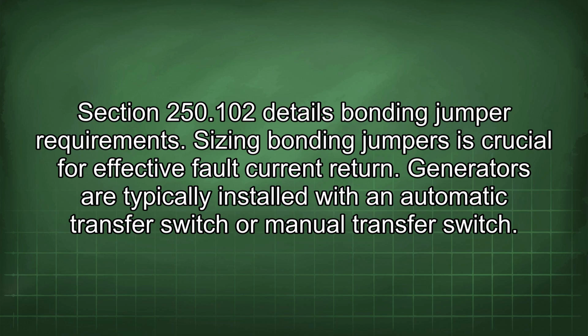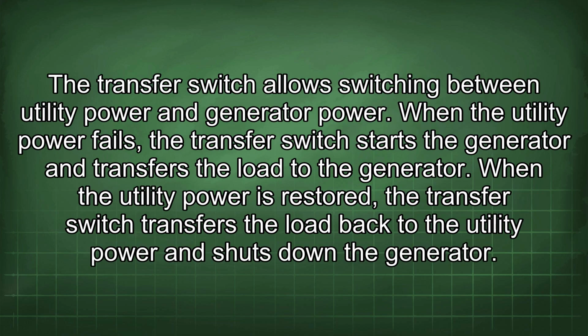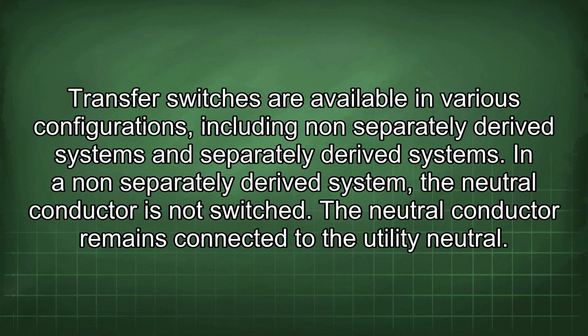Generators are typically installed with an automatic transfer switch or manual transfer switch. The transfer switch allows switching between utility power and generator power. When the utility power fails, the transfer switch starts the generator and transfers the load to the generator. When the utility power is restored, the transfer switch transfers the load back to the utility power and shuts down the generator. Transfer switches are available in various configurations, including non-separately derived systems and separately derived systems.